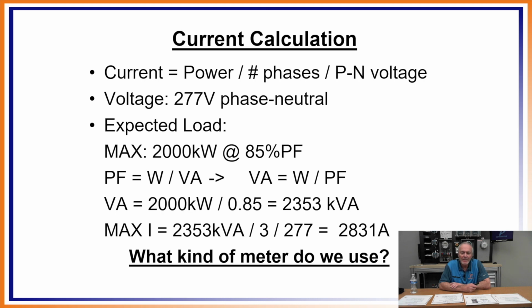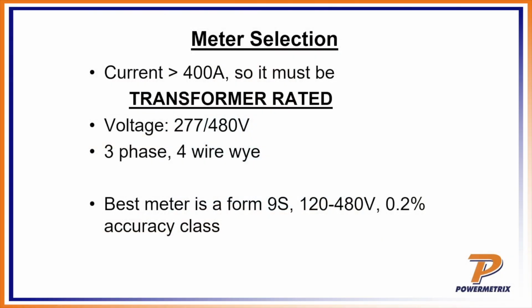So what kind of meter do we use? Remember where the break is, it's on the current, right? So we know that this is well over what we could use a self-contained for, the 2,831 amps. Right? So it says right there 400, and you can say 400, there are 600 available, but we'll say over 400, but this one's definitely no question. So it's going to be a transformer rated. So the best meter would be a 9S here, and you can see where it's got the multi-range there from 120 to 480 volt, and it would be a 0.2% accuracy class.